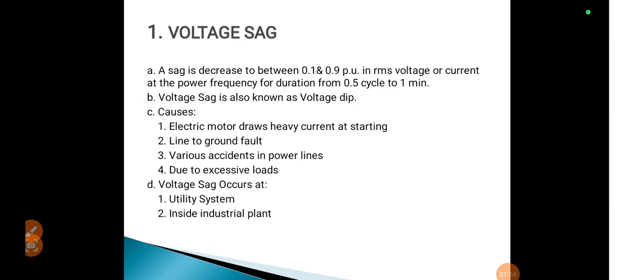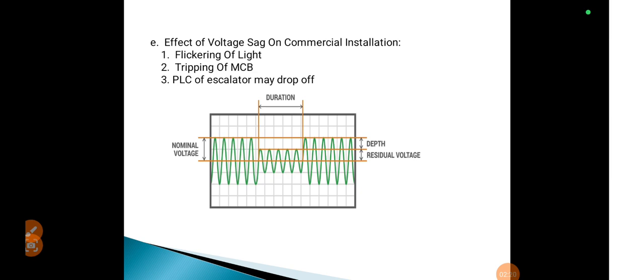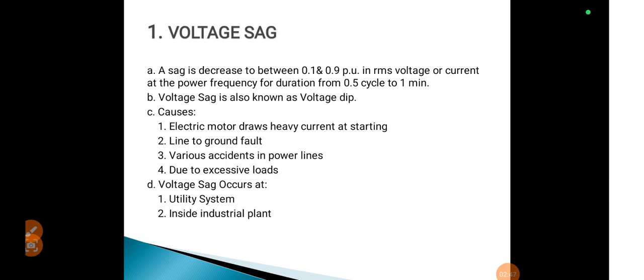Voltage sag occurs due to faults on transmission or distribution networks, faults in the consumers' installations, connection of heavy loads and startup of large motors. At the starting of heavy loads and large motors, the sag can occur. Voltage sag can occur at the utility system or industrial plants. The consequences or effects of voltage sag are the malfunction of information technology equipment, namely microprocessor-based control systems, PLCs, ASDs, etc., that may lead to a process stoppage. Next is the tripping of contactors and electromechanical relays. Next is the disconnection or loss of efficiency in electric rotating machines.